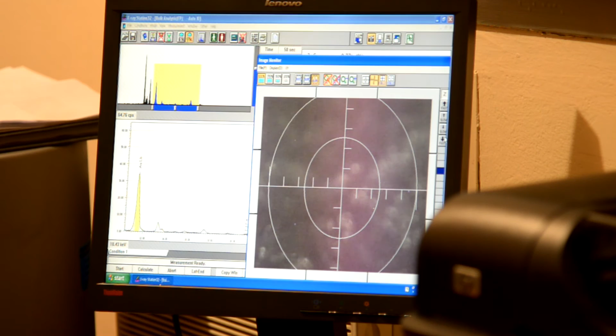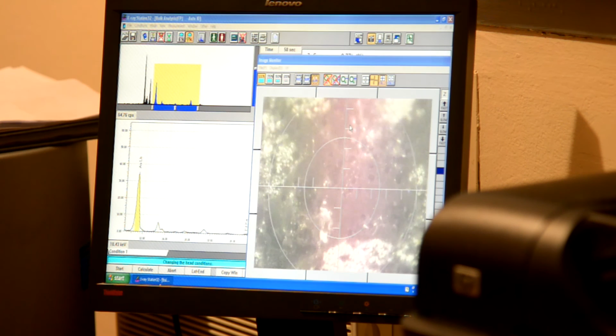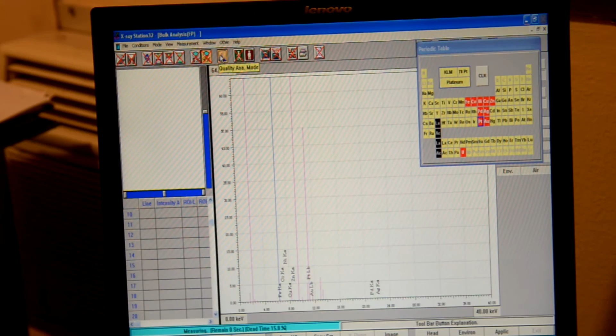Okay. Now, what you're gonna do is, no drilling, no nothing. Just nothing. What we do is now we adjust the specimen, so we want to go to more or less this area of the specimen, and we adjust the sharpness. Now we adjust the sharpness, and let's go. So the machine is starting right now, and we're gonna see the picture exposed. But I'm gonna switch to this kind of screen, I like it better. And soon we see the reading. It's gonna take approximately 43 seconds more, and we're gonna have the results.